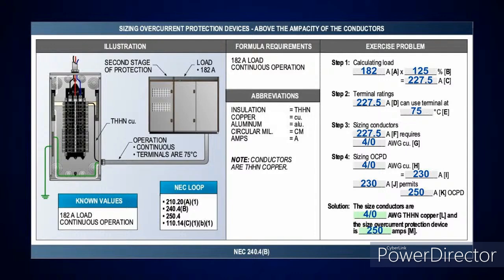250 amp. See what I'm saying? I don't have the standard sizes on speed dial, but if you look, this is 240.4B. Now, what is one of the things I said about 240.4B? I said that's for devices rated 800 amps or less. Once I'm above 800 amps, then I'm in 240.4C.